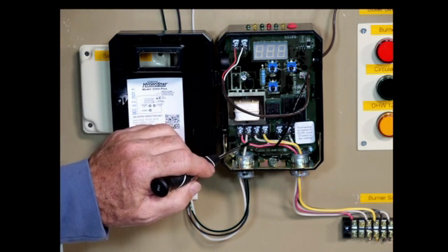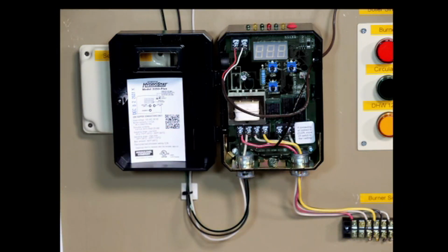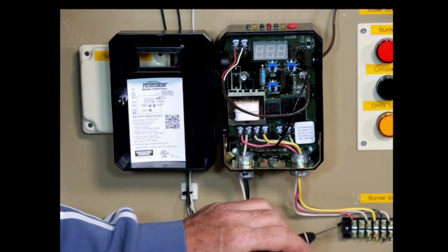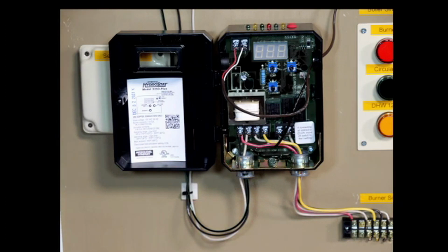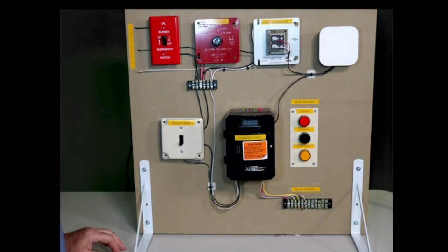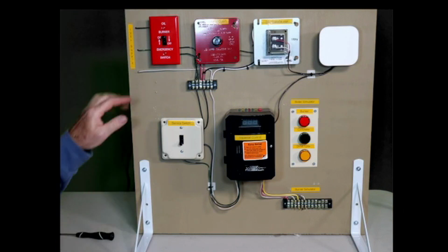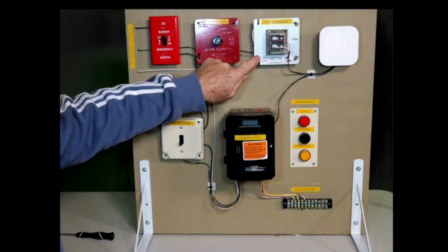Now in some controls, I like to send power down continuously to the burner control, the primary control, so that it's powered on all of the time, and use the limit to fire the burner. So if the power is on the remote switch, it's going to send power to our thermal cutoff, which also powers the transformer.